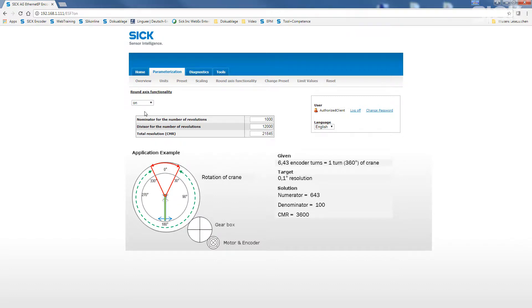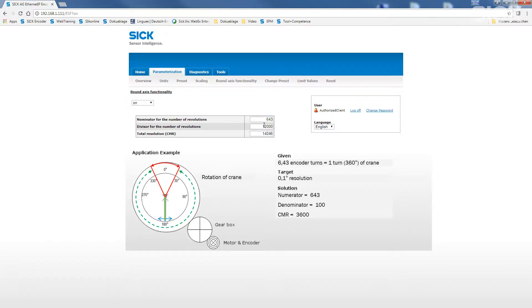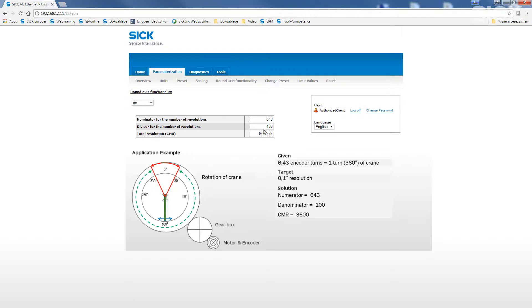In addition, an application example is displayed on this screen. For our demo application, we need to use the following values for a correct adaption of the encoder. Set the nominator to 643 and the divisor to 100. All new values must always be confirmed with the enter button. This way, 6.43 turns of the encoder equal one turn of the application.